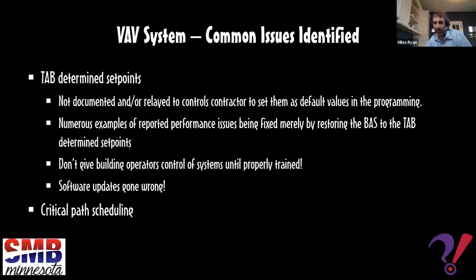All right, so during the TAB process, as Mark kind of talked about, there's a lot of set points that need to be determined by the TAB professional and then relayed to the temperature controls contractor. And I'm talking to the TAB professionals on the call now, a lot of times we see that information is not clearly defined in that final consolidated TAB report. That information has to be documented in the TAB report. Additionally, it needs to be relayed to the controls contractor so they can take those values and make those the default values for the set point on the automation system.